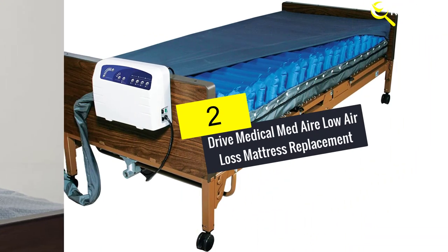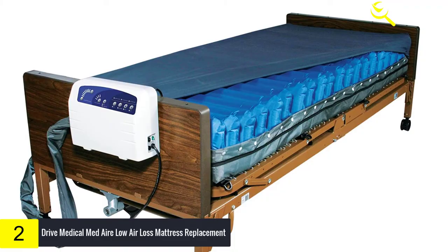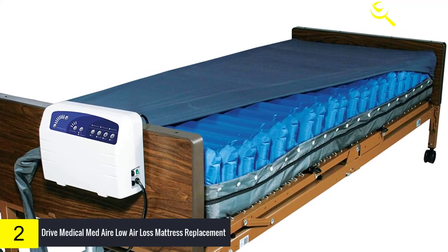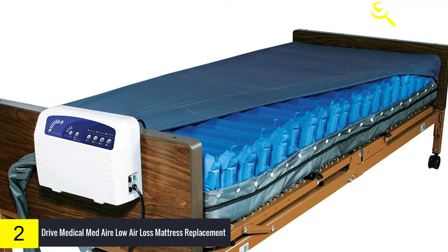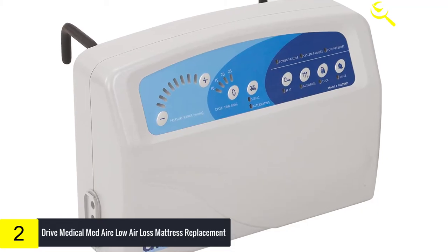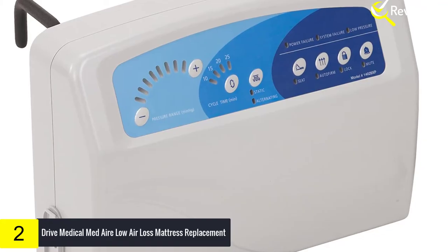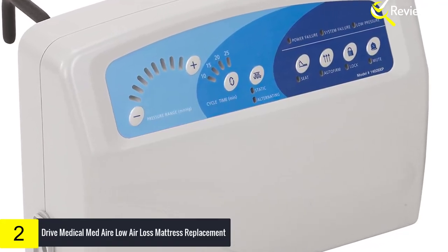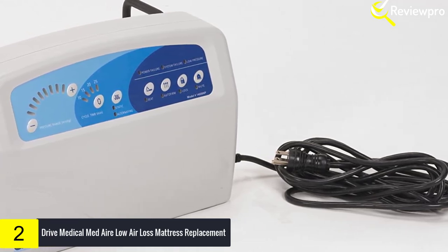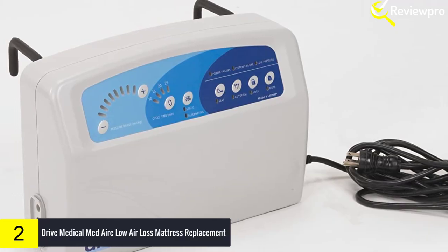At number 2, we have the Drive Medical Med Aire Low Air Loss Mattress Replacement. This alternating pressure mattress replacement system is designed for the prevention, treatment, and management of pressure ulcers. The mattress operates in alternating pressure mode and is ideal for use in hospitals, nursing homes, and home care. Individual bladders are easy to remove and replace, and three air cells remain static to enhance patient comfort. LED and audible alarms activate when pressure falls below 10 millimeters of mercury, and the cell-on-cell design prevents the patient from bottoming out during a power failure.